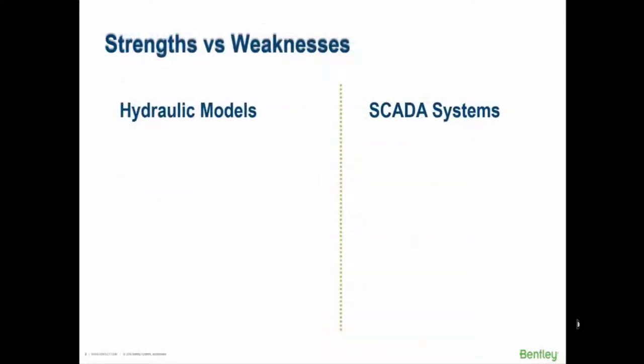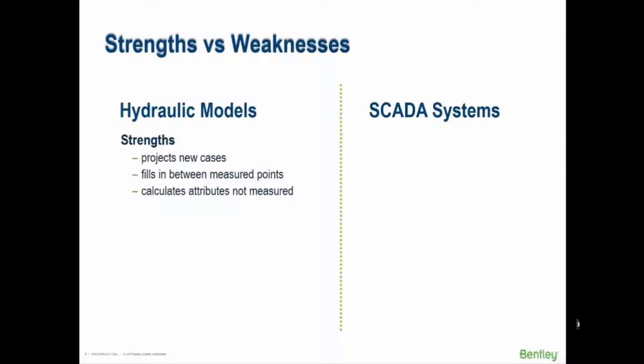Let's look at hydraulic models versus SCADA systems. On one side, the hydraulic model can solve for things that haven't happened yet. If you have data at a few points, it can calculate results for places in between known measured points in your system. It can calculate things you can't measure — things the SCADA system isn't measuring — like hydraulic grade line or velocity, which you don't measure directly.